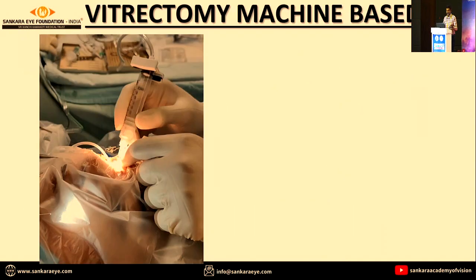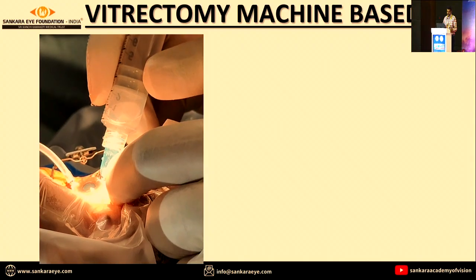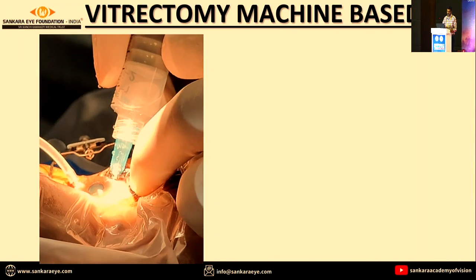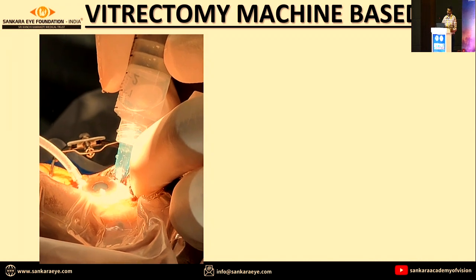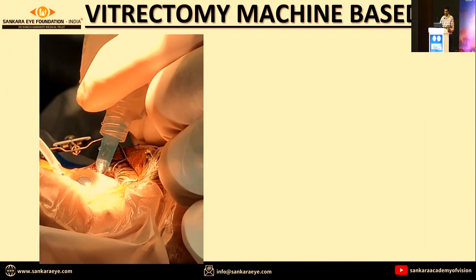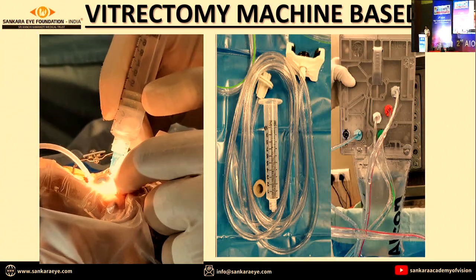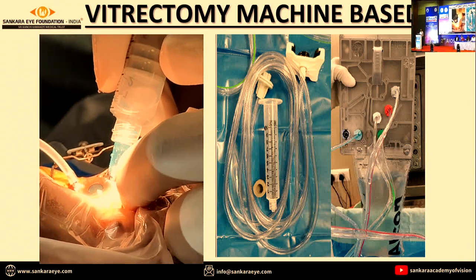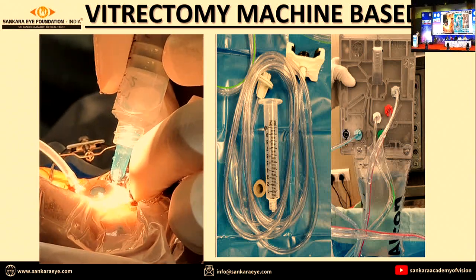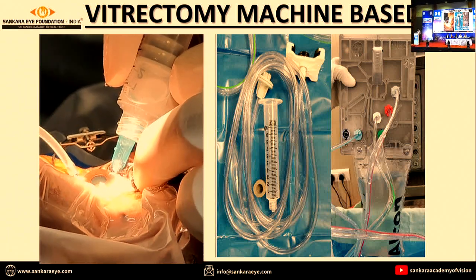Now coming to the classical vitrectomy-based approach, you can see a small video wherein the silicone oil is being removed with an extrusion syringe which is connected to the vitrectomy machine. Here you can see the oil comes very slowly into the extrusion syringe. And for this, the image to your right shows all the equipment which is required. Basically, you require a vitrectomy machine, the cassette, the tubings, and the syringe as shown in the video.